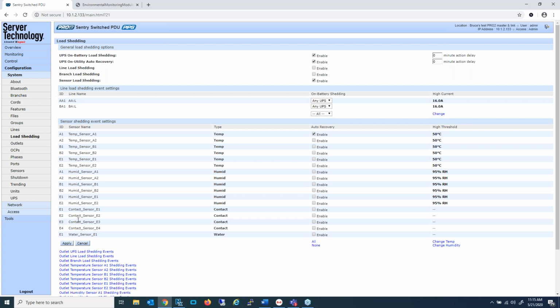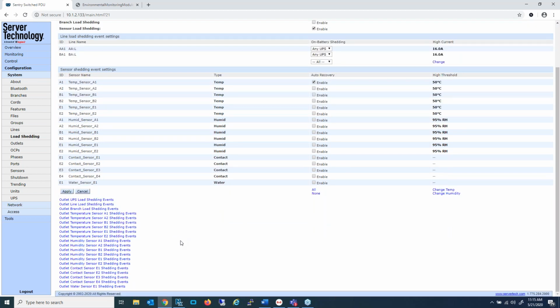It also adds 4 contact closure monitoring points that can be wired to normally open or normally closed contacts, and a transition from one to the other is the trigger for the load shedding event. Finally, the environmental monitor control unit supports a water sensor rope that, positioned somewhere in the data center where there might accumulate moisture, if it gets wet, we can trigger an event that will switch outlets off that you have pre-selected.